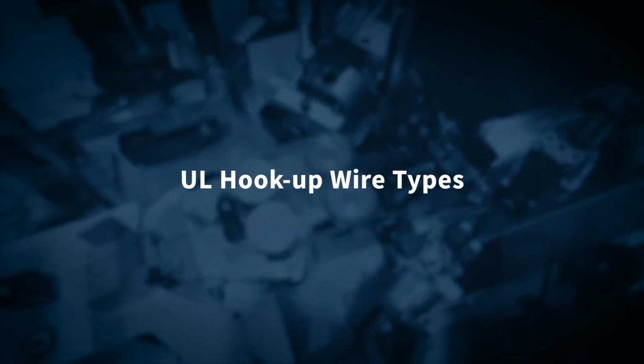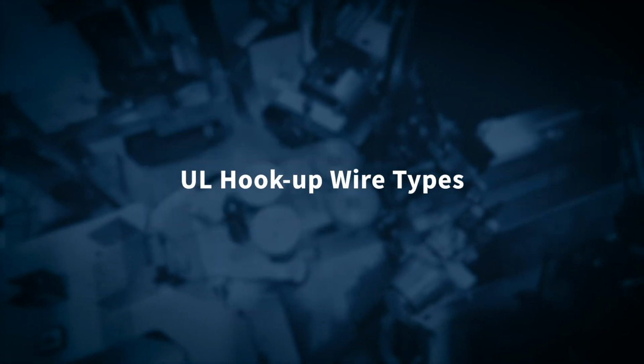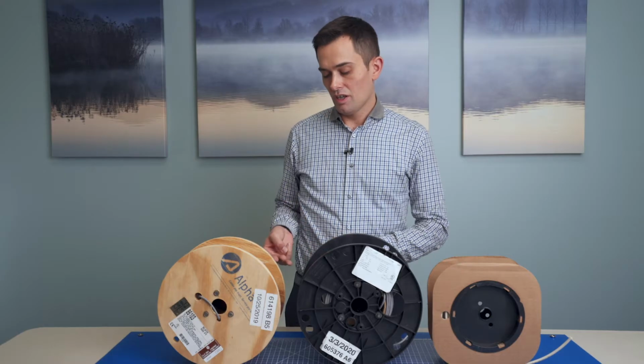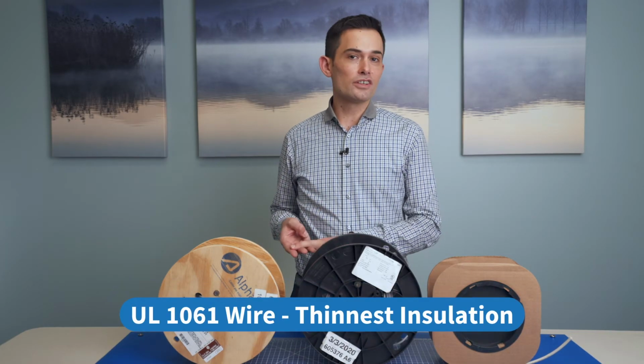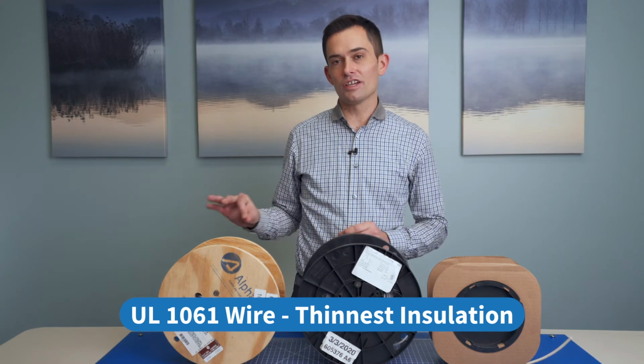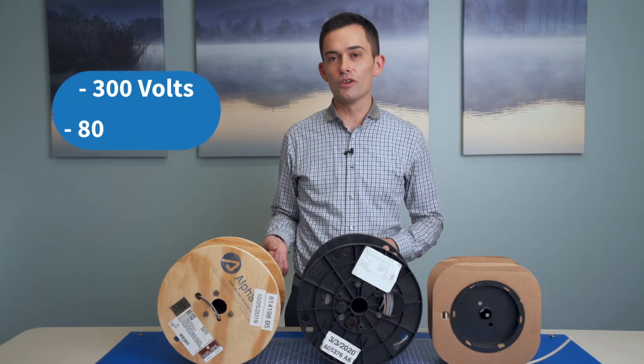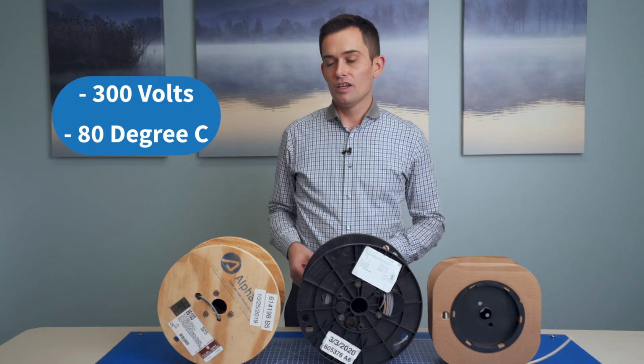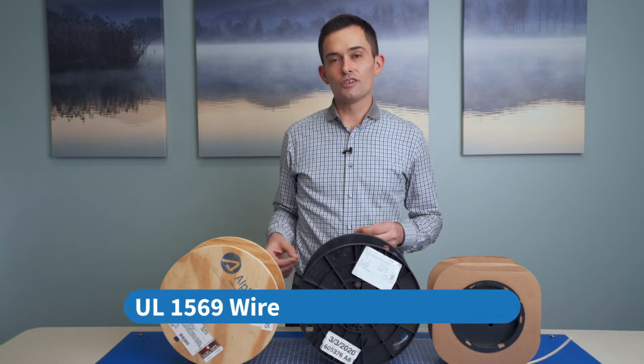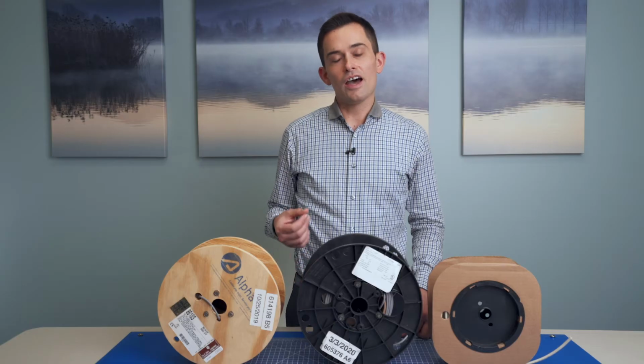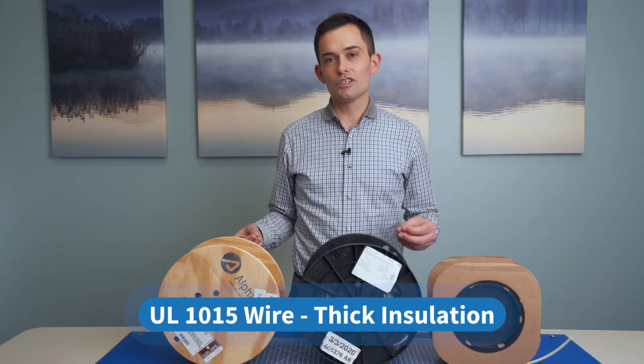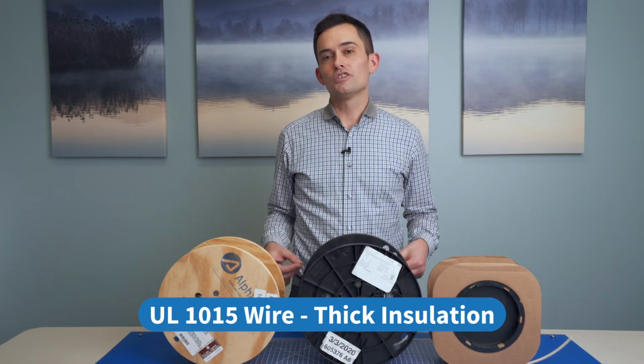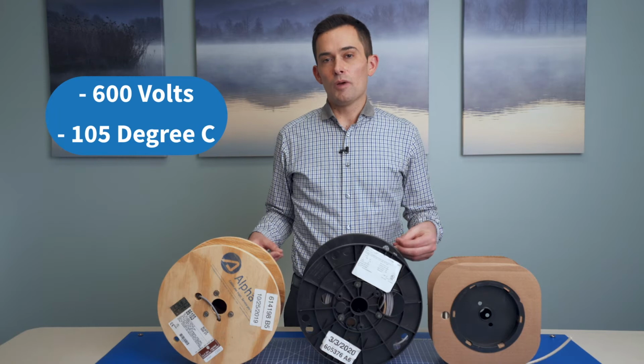So when it comes to hookup wire selection, we usually like to steer people into one of three different UL wire types. The first one is UL 1061, which is the thinnest insulation. It's rated for 300 volts and 80 degrees C. A medium insulation is a UL 1569. That's also rated for 300 volts, but it carries a 105 degrees C rating.